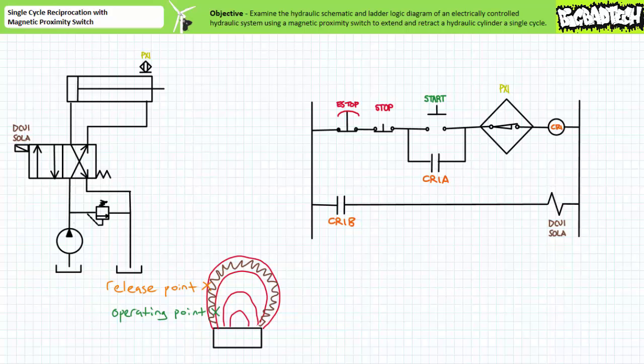Note in contrast to a regular physical limit switch this means of detection needn't be binary in nature — the mutually exclusive decision of yes it's there or no it's not — but could be a measurable quantity relayed not by a proximity switch but rather a magnetic proximity sensor or transducer. A sensor returns not a mutually exclusive on or off signal but rather an analog voltage or current value proportional to the measured quantity. This value could be relayed to a computer or PLC where programmed instructions make decisions, or a digitized representation could be stored for later analysis.